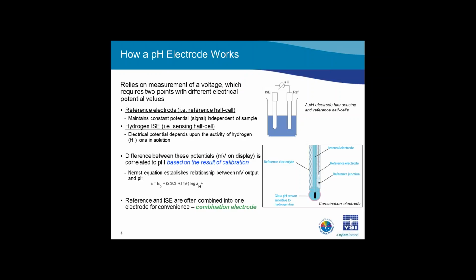pH measurement with a glass pH electrode relies on the measurement of a voltage. In order to measure the voltage, 2 points with different electrical potentials, basically electrical signals, are required. The reference electrode is designed to maintain a constant potential that is independent of the sample. The reference is sometimes referred to as a reference half cell. In contrast, the sensing portion of the electrode, sometimes referred to as the hydrogen ISE, or a sensing half cell, provides a potential that is dependent upon the sample pH. The millivolt output seen on the pH meter represents the difference between these potentials. This measured voltage is correlated to the pH of the sample based on the Nernst equation. Therefore, both the reference electrode and the hydrogen ISE are needed when determining pH.